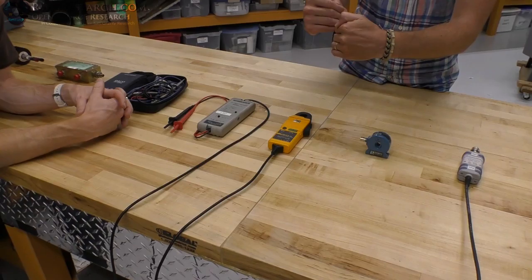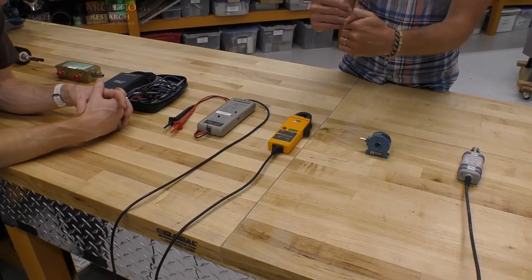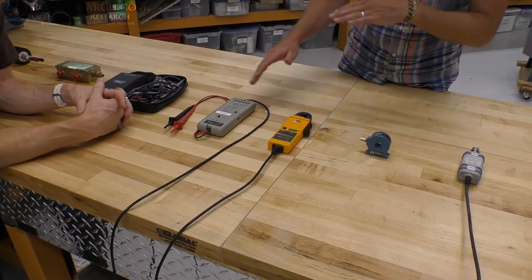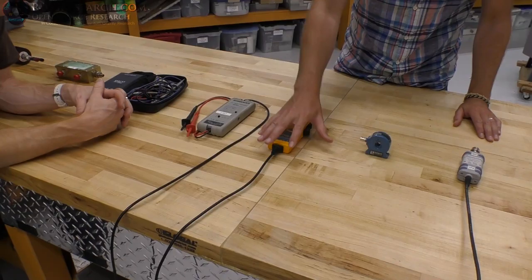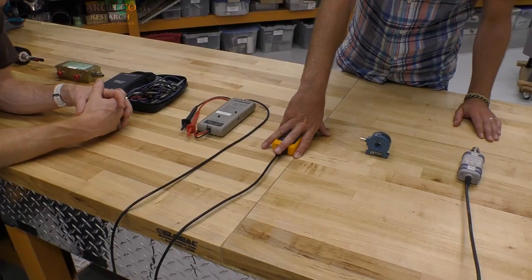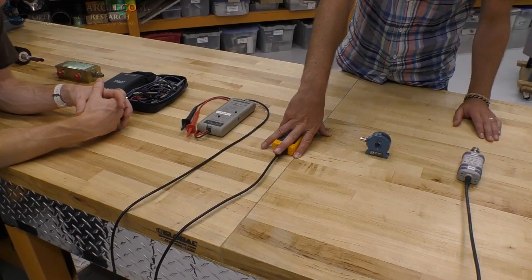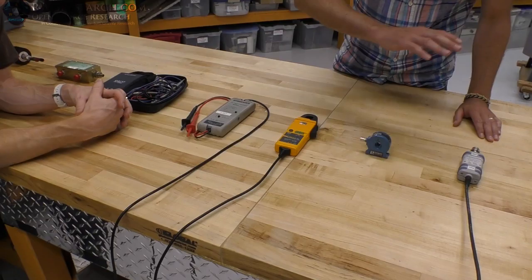If you've got 90 degrees phase difference between voltage and current, you've got zero power. Now if your phase is off, if you've got say 90 degrees, or 80 degrees, or 70 degrees, this is making a huge difference to your output power. It goes between maximum power and no power whatsoever. You've got to totally get a handle on that. That's all about trying to make sure that the voltage oscilloscope readings are in alignment and correct with the current measurements on the oscilloscope. Then you need to actually do some maths functions in order to get a true power measurement. It's not enough to just multiply voltage by current. You need to get the whole thing on the oscilloscope and do it properly.